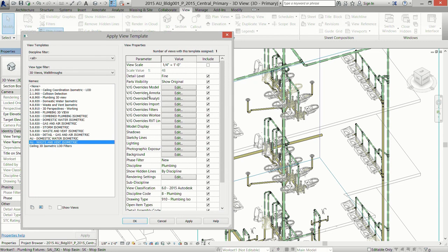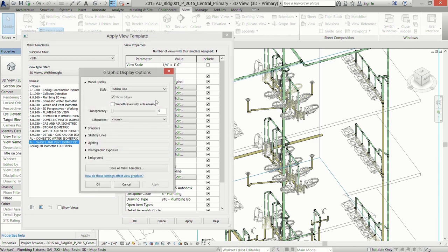That quick template change just isolated the entire waste and vent system. As explained, you set it up once, add it to your master template, and it's the most time-effective approach we've found for quickly displaying a system. These settings don't have to be set exactly like ours — this is just what we've found over 15 to 20 projects works best and prints the best. Feel free to adapt as you please. We like to set the detail level to 'Fine,' which shows the actual pipe instead of a 2D outline.